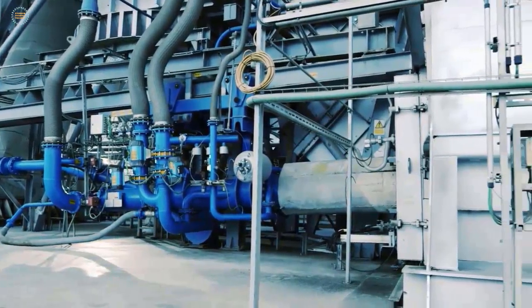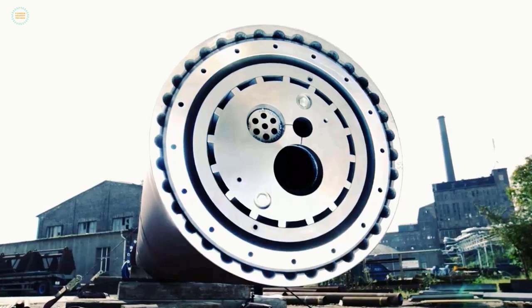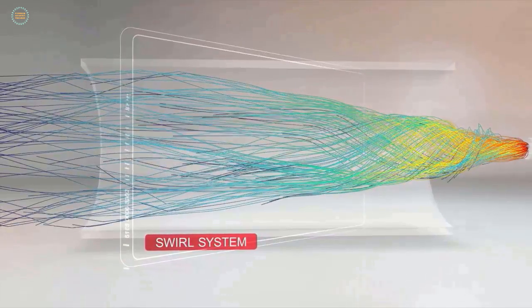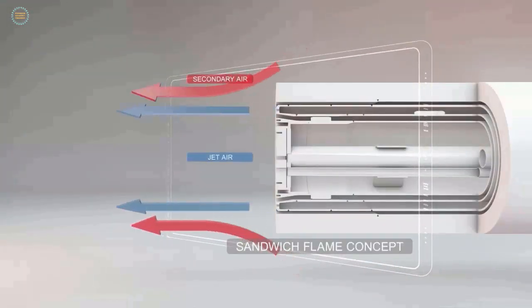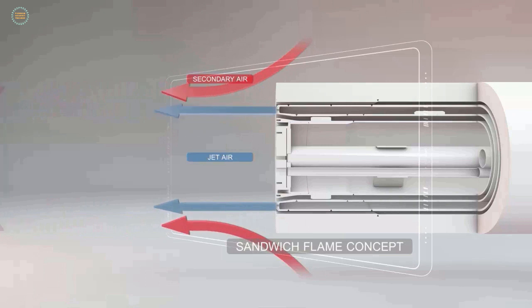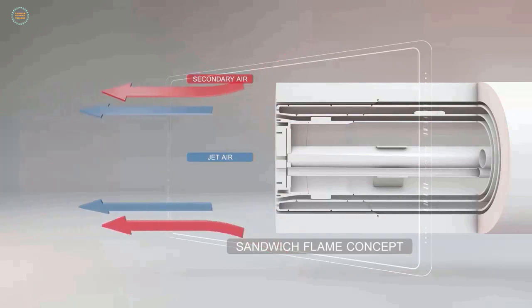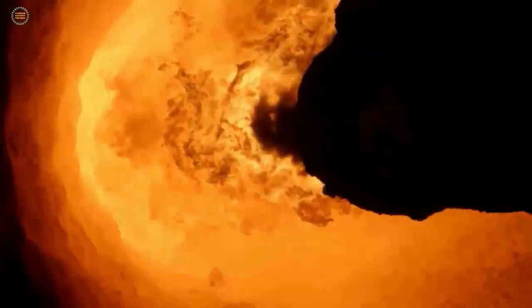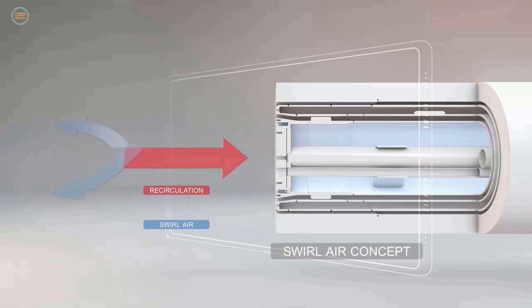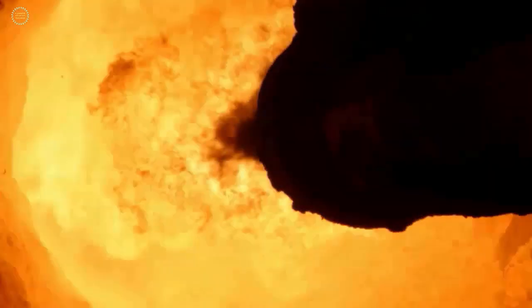The PyroJet burner made by KHD — the PyroJet system is based on the jet air effect. Conventional and alternative coal and other pulverized fuels are injected through an annular gap, ensuring the most efficient mixture between fuel and secondary air and hence complete combustion. The jet air emerges from the axial nozzles, creating a strong suction effect and the most efficient mixture between secondary air and fuel. This sandwich flame concept ensures efficient combustion by saving energy while keeping a stable flame. The swirl air emerges from a multitude of slots in the centrally located swirl element, creating a low-pressure zone in front of the burner so that already burning particles are recirculated to the base of the flame.